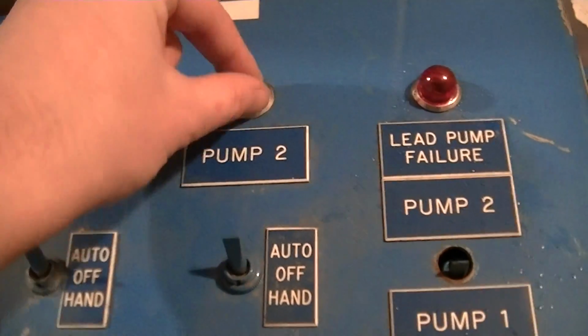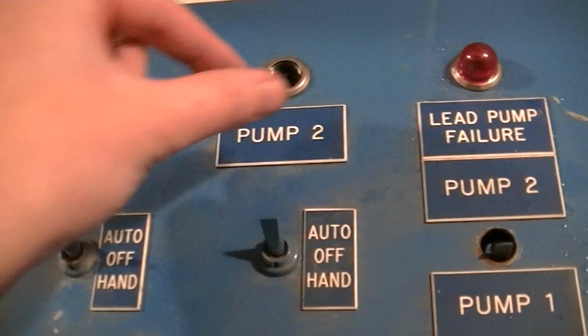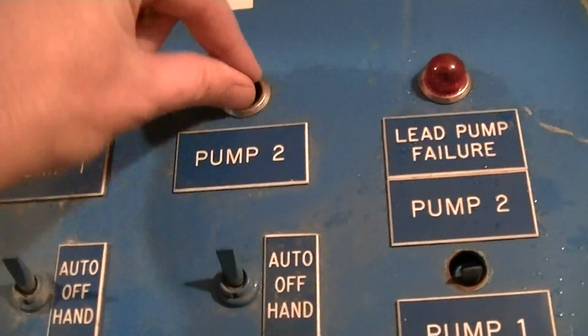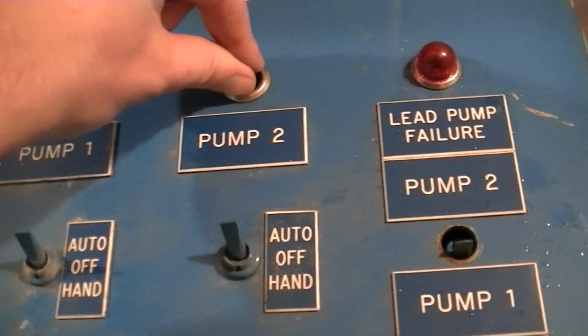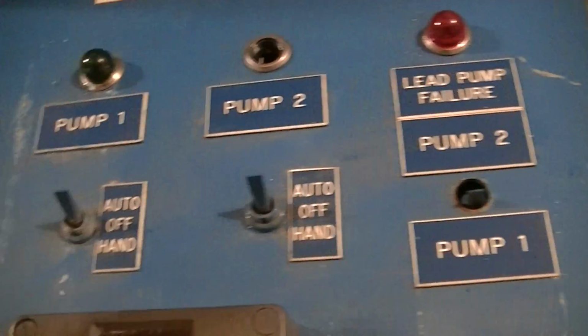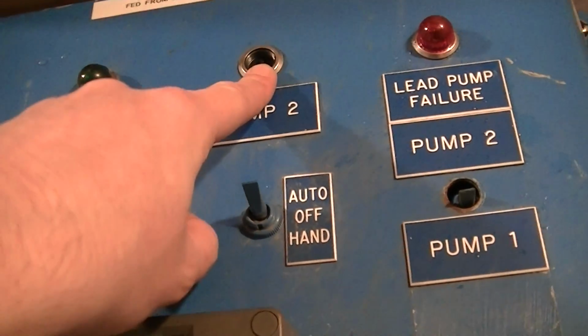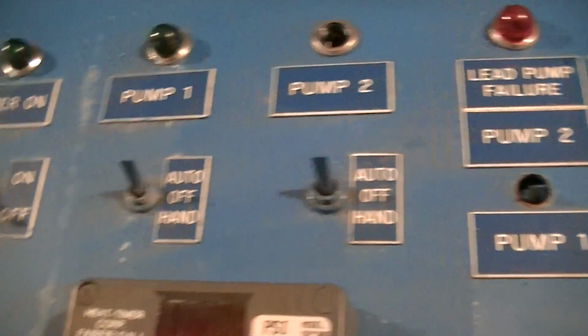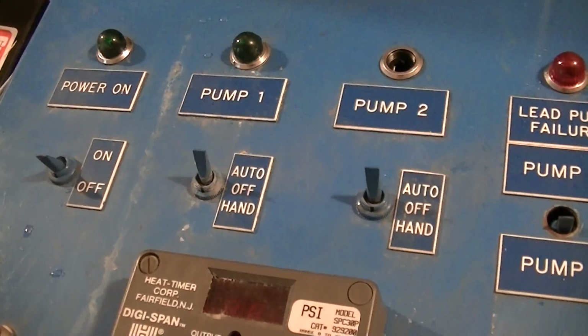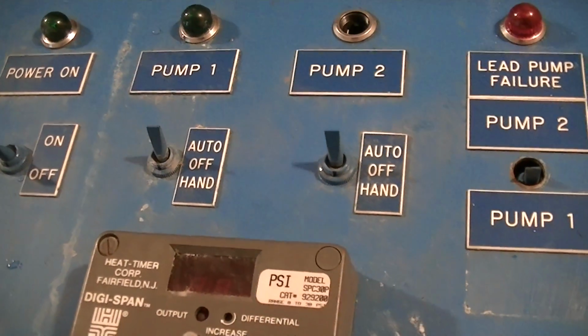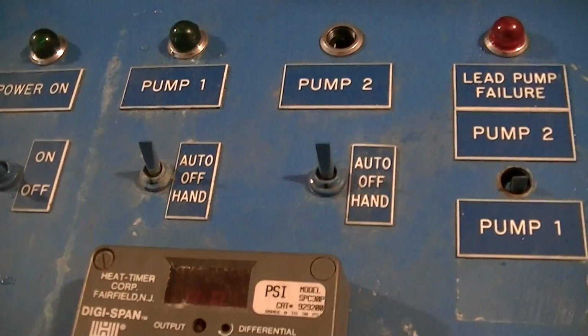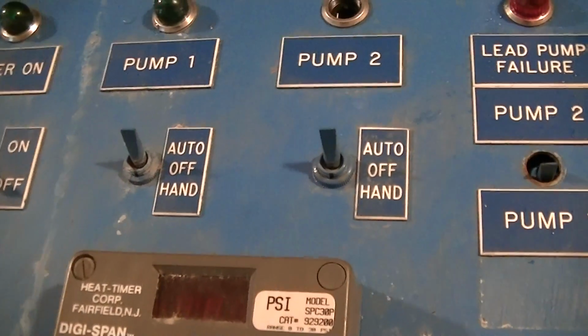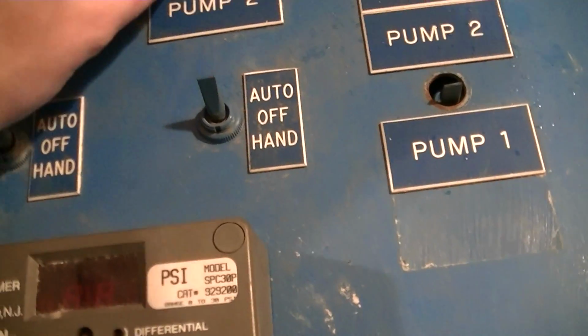But basically it's so that whoever is relamping the panel doesn't inadvertently stick a much lower potential lamp in there, and then as soon as it makes electrical contact and the lamp turns on, it explodes. If the contacts in the lamp holder are alive when the guy puts the lamp in, the lamp explodes, and of course you've got broken glass embedded in the guy's fingers, and you have the remains of the lead-in wire assembly, which have good 120 odd volts on them.